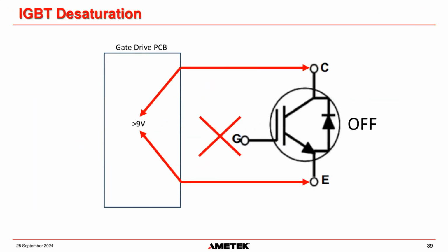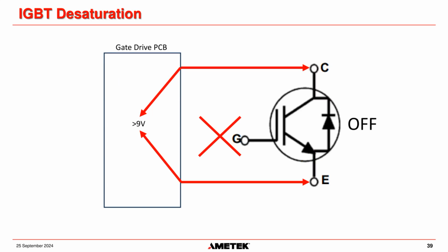But if we get a situation where it goes above 9 volts, then the gate drive board says, nope, that's not possible. That means that our IGBT has too much current flowing through it. Okay, that's what desaturation means. When an IGBT goes out of its saturation zone, too much current is flowing through it. It's not in its perfect zone anymore. And the more current that flows through, the higher voltage will be measured across the collector and the emitter. And that means the IGBT could be getting ready to fail at any point. So what we try and do is remove the signal from that IGBT as quickly as we can to prevent the current going through the IGBT and from it destroying itself. And then what will happen is on the gate drive board, there will be an LED that says desat, okay?